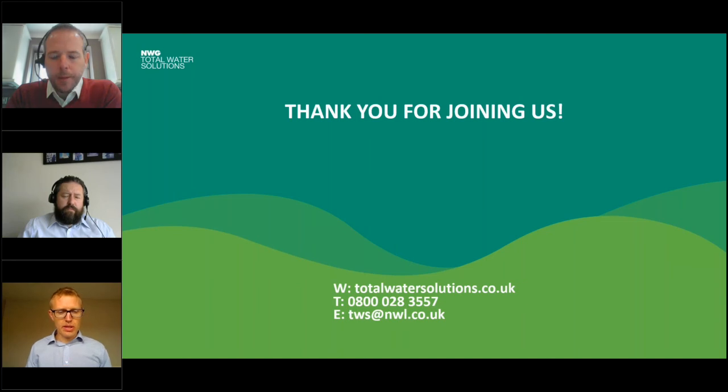So it takes background temperatures every 3 hours, so you get that 24-hour profile of what's happening in the system. As Michael said, that's important because overnight some hot water might get back up to the right temperature, and you'll miss that if you go during the day to test it. And within the 3-hour window, it also listens for usage.